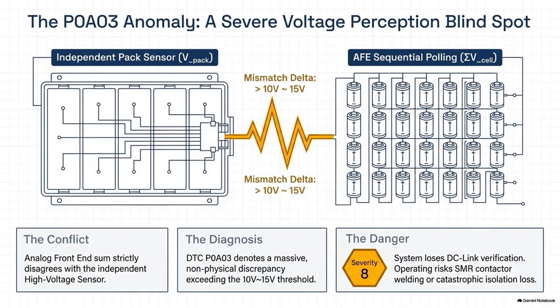But beyond parasitic resistance and signal latency, there is a third root cause we need to analyze. Right. Actual hardware faults and configuration errors, specifically something known as sensor drift. Okay, this relates to the extreme operating temperatures inside the high voltage distribution box, right? Yes, exactly. Inside that box, you have main contactor relays snapping shut, high voltage fuses, and thick copper routes carrying all those hundreds of amps. These components generate immense localized heat. I can imagine. And sitting right next to these screaming hot components on the printed circuit board are the total voltage sensing circuits. Now wait, I want to dig into how those sensors actually work.